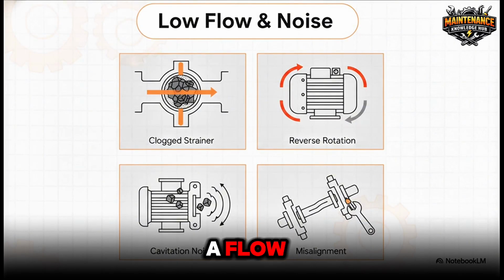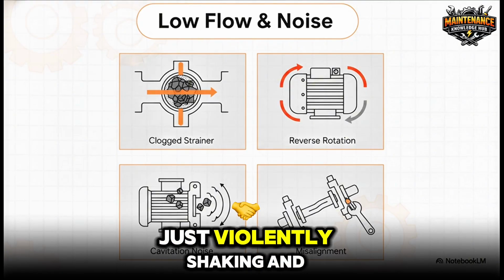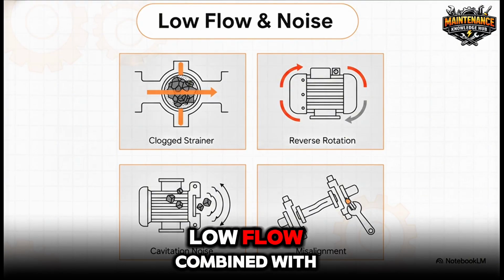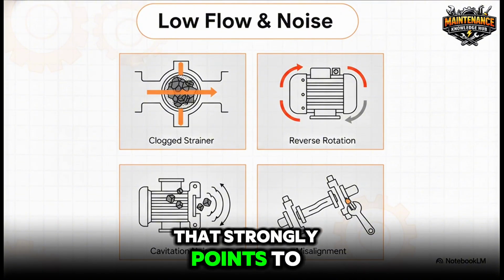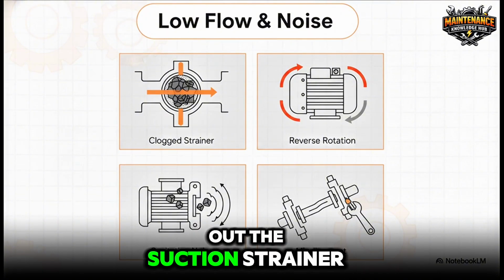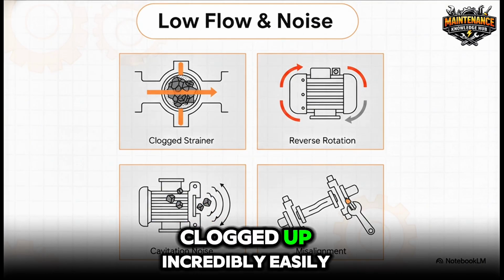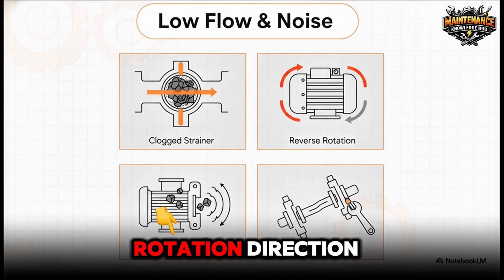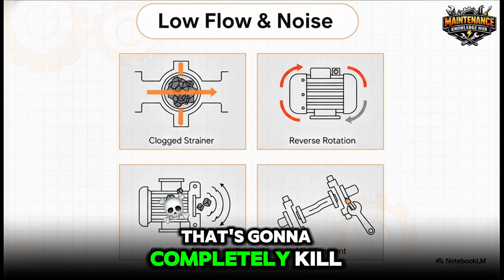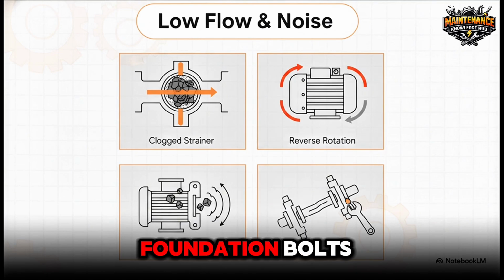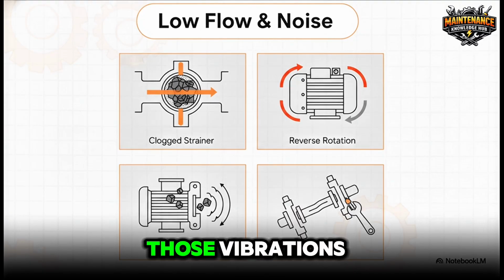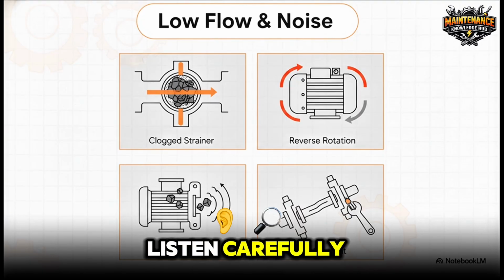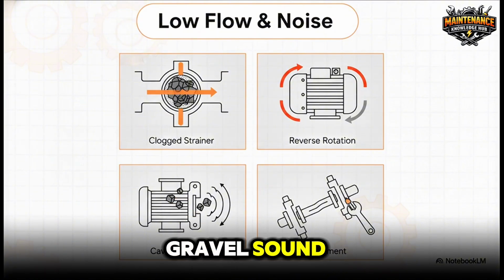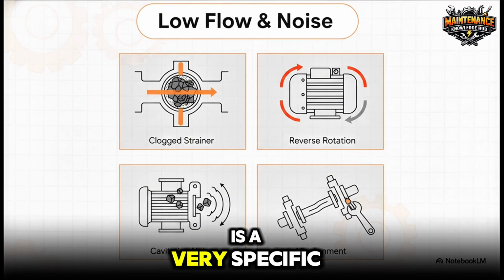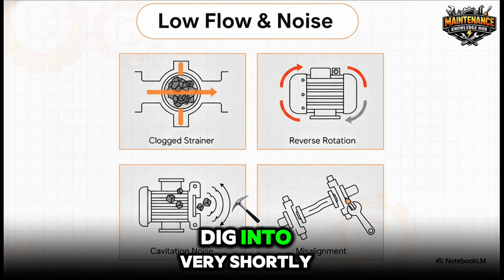Now, sometimes you do get flow, but it's super weak, or the pump is just violently shaking and making an absolute racket. Low flow combined with excessive noise strongly points to mechanical clues. You're going to want to clean out the suction strainer. It basically acts like a filter and gets clogged up incredibly easily. Also, check the motor rotation direction. If it's running backwards, that's going to completely kill your flow. Check for any loose foundation bolts or maybe a coupling misalignment that's causing all those vibrations. And here's a big one. Listen carefully. Do you hear a distinct gravel sound, like a bunch of actual rocks tumbling around inside the casing? That is cavitation, which is a very specific, highly dangerous issue that we are going to dig into very shortly.